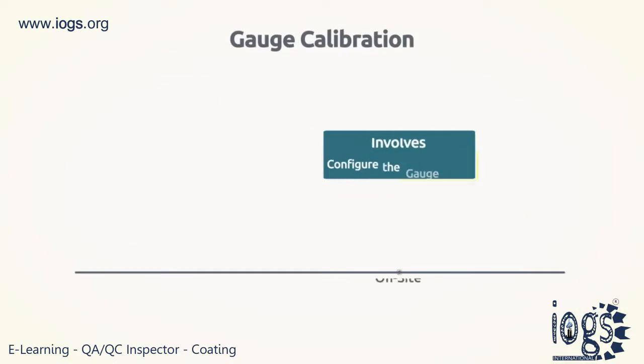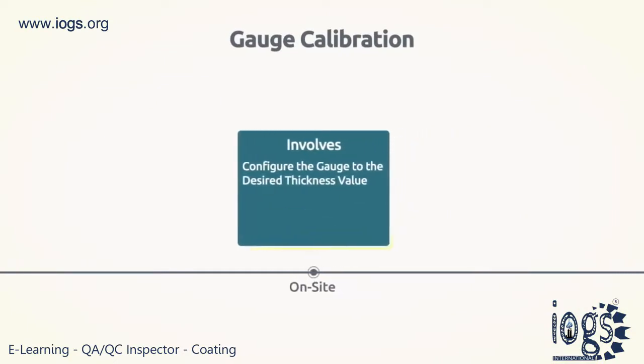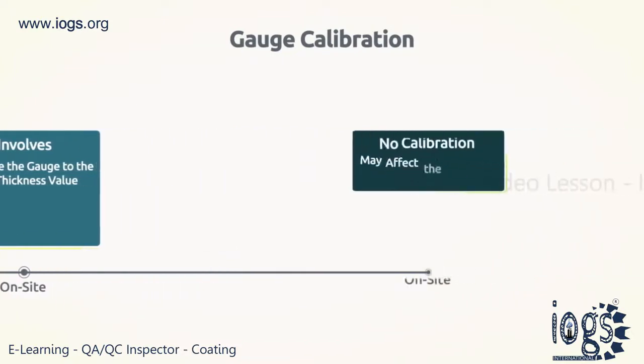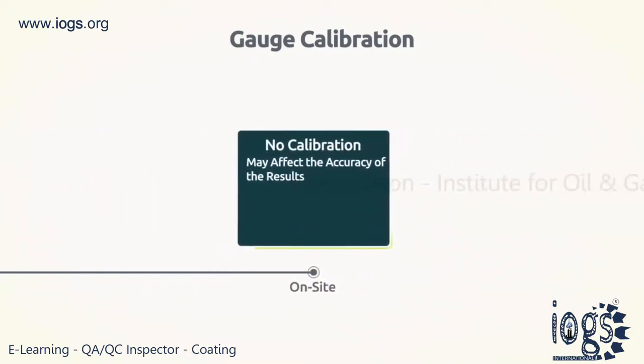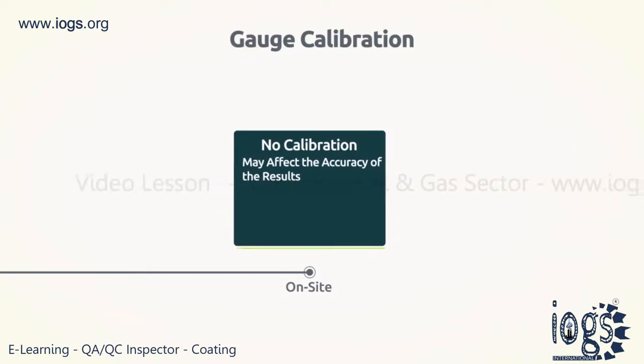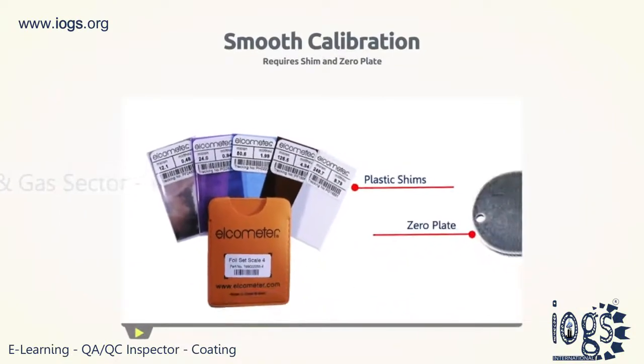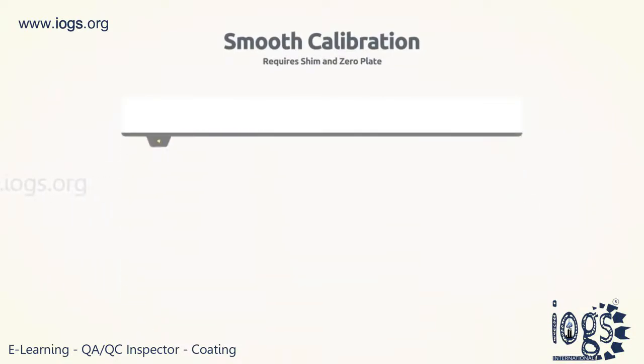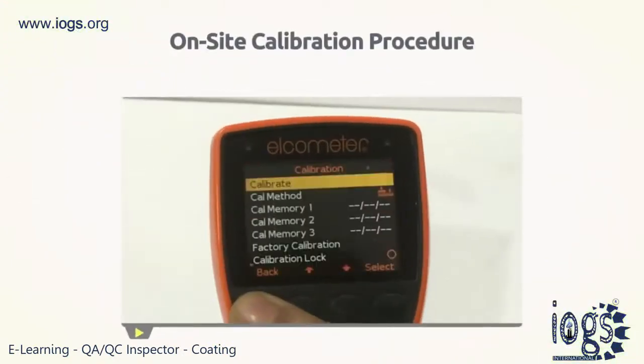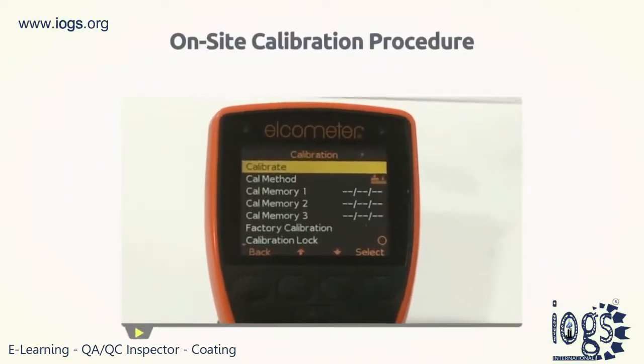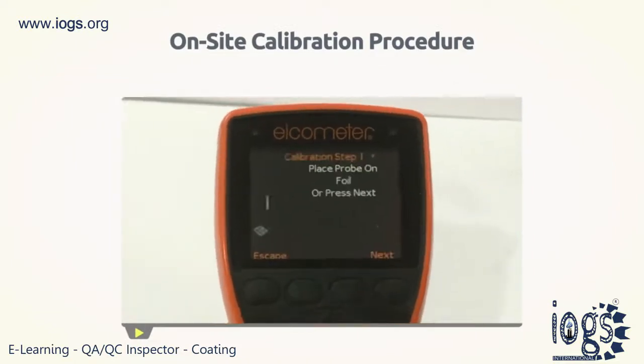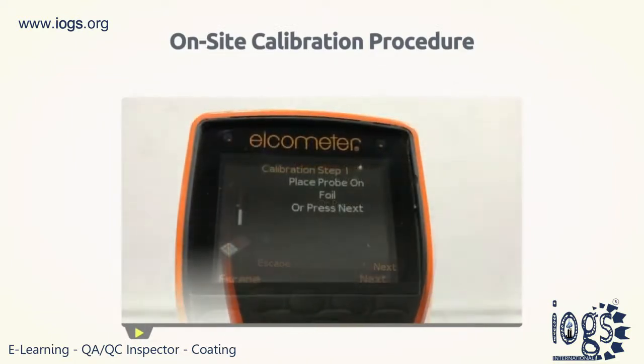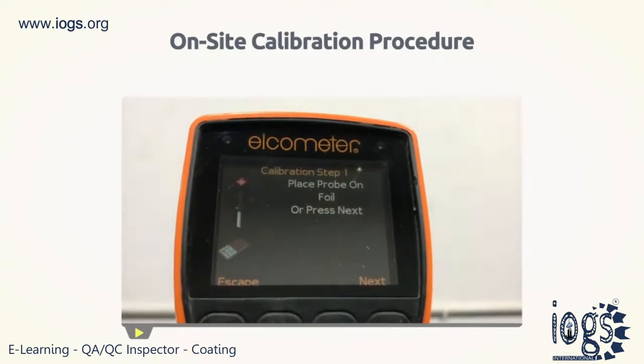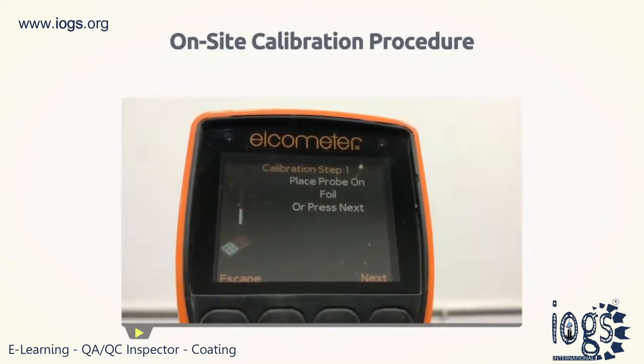Calibration adjustment involves configuring the gauge to your desired thickness values. It is best to calibrate the gauge on site before taking the gauge reading of the coated surface. Anything contrary to this may affect the accuracy of the results. Calibration is done by choosing the proper plastic shim with the above target DFT value, alongside an uncoated base or zero plate. To calibrate the gauge, press the Cal soft key present on the gauge, locate the Calibrate option on the screen, and choose the same. You will now be presented with simple on-screen instructions that you can follow to calibrate the gauge successfully.